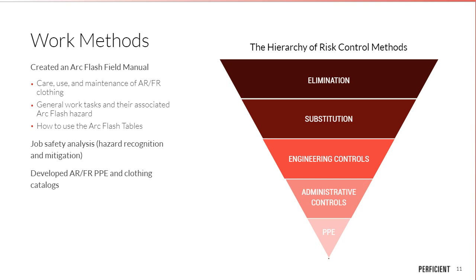However, utilities like mine have been in operation for at least the last 100 years, so there are some sites that didn't have this philosophy. That could be implemented at different levels or with limitations. Another typical engineering control is to have protection settings that someone changes before performing work, adjusting how fast the system disconnects to lower the arc energy.